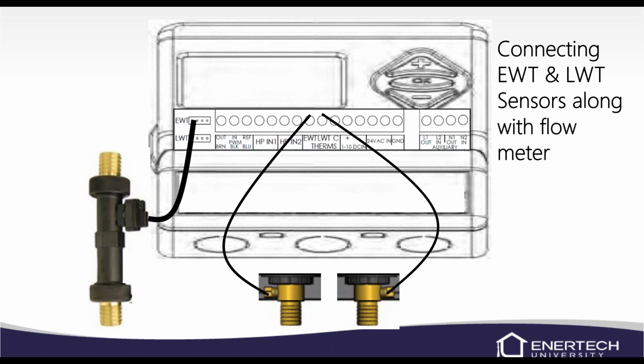It's kind of confusing because it does say EWT, LWT on the far left, and that's actually where the Molex plug goes for the entering water flow meter, not the actual water temperature. The thermistors go into the EWT, LWT therms. That stands for thermistors. A little bit confusing, but not too bad.